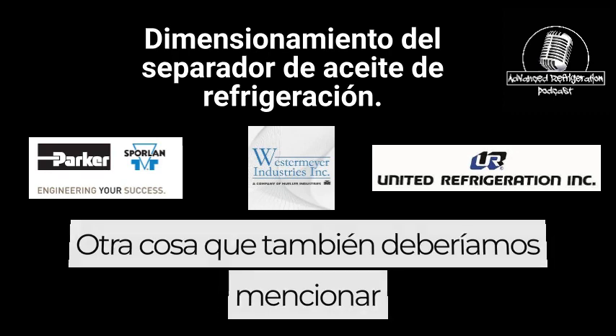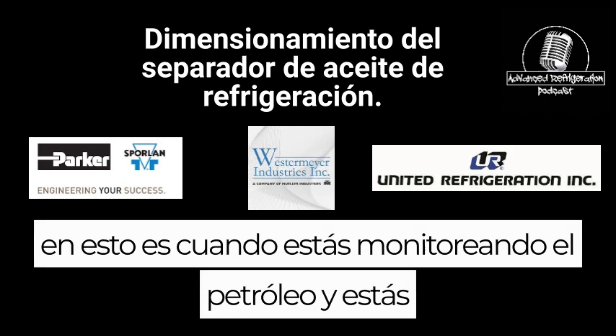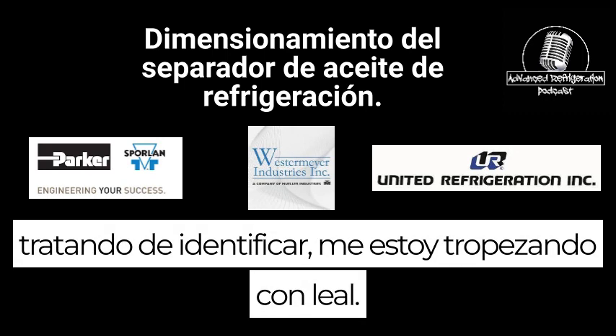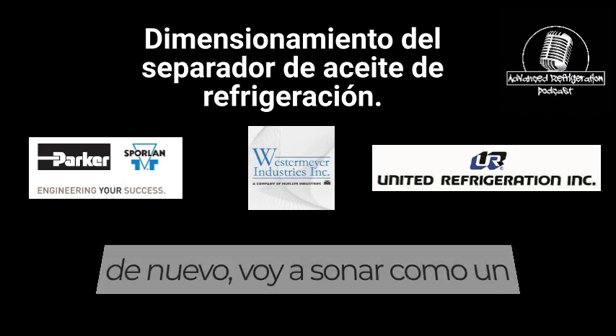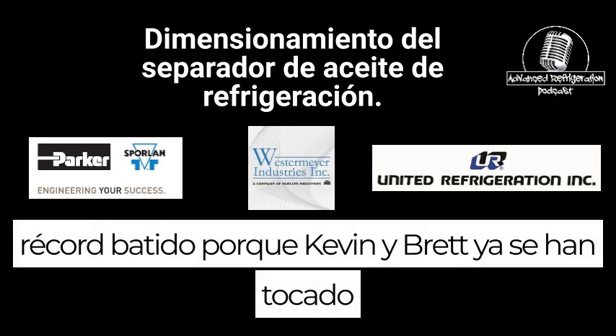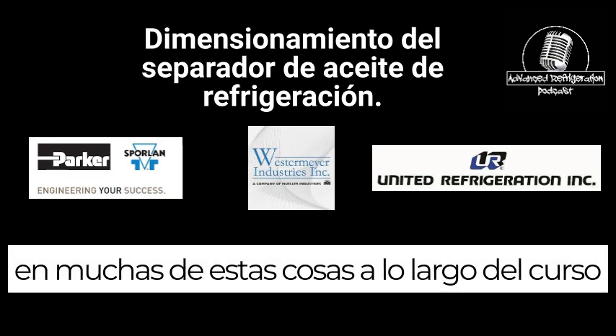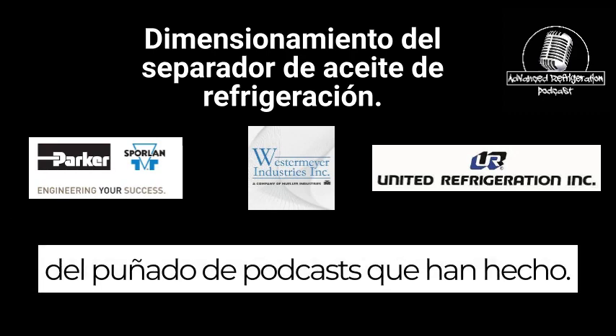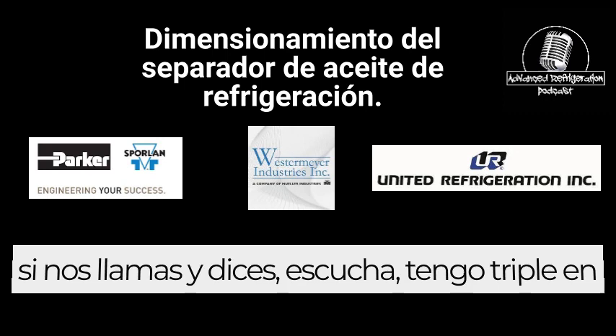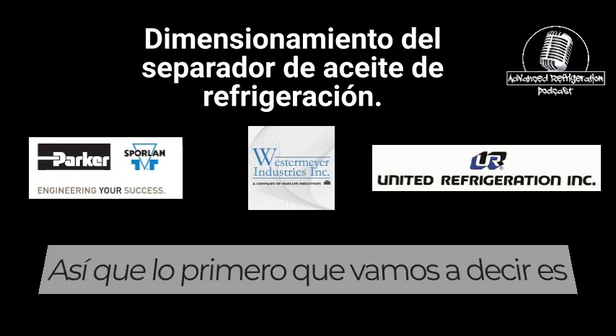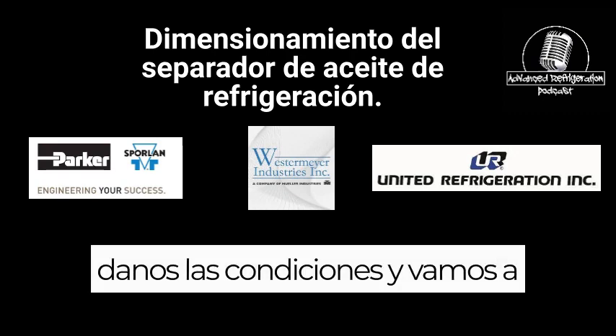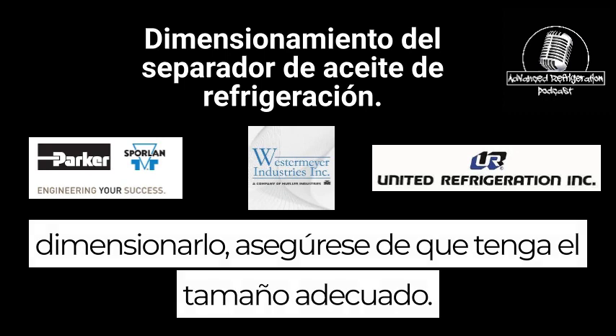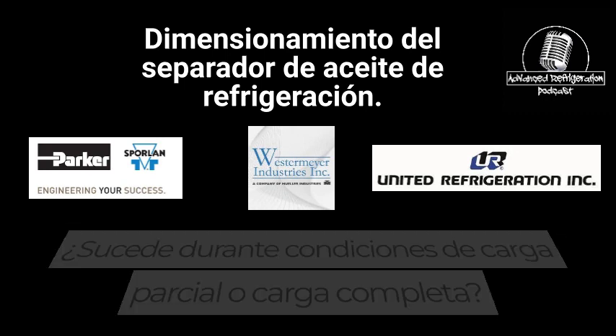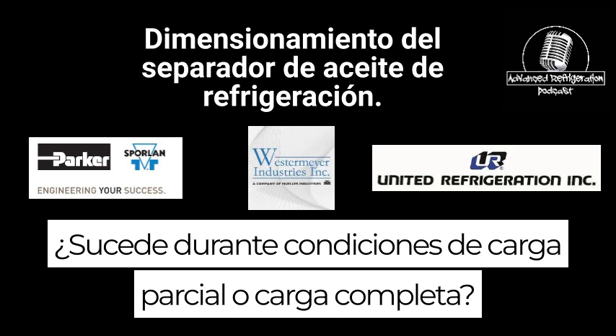Another thing we should probably bring up is when you're monitoring oil and trying to identify why you're tripping on low oil. Again, I'm going to sound like a broken record because Kevin and Brett have already touched on a lot of this over the course of the handful of podcasts they've done. If you call us and say, listen, I've got a trip on low oil, I'm having some issues, a couple of things. First thing we're going to say is give us the conditions, and we're going to size it and make sure it's sized properly. Another thing we're going to ask is, does this happen during part load or fully loaded conditions?